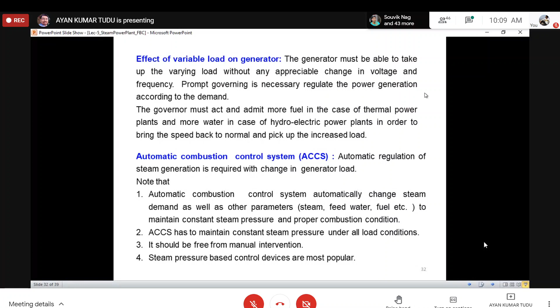The problem with the variable load in a thermal power plant is that with an increase in load, what will the governor do? The governor will admit more steam to maintain the turbine speed. Now it becomes very difficult to get quick and good combustion as well as steady steam pressure, even with increased fuel supply and rapid governor response, because efficient combustion requires the coordination of many services.